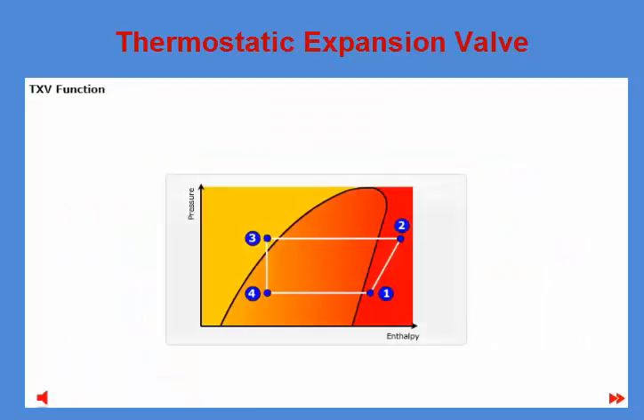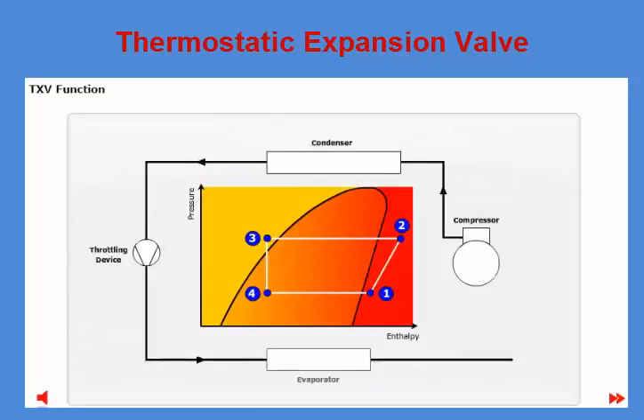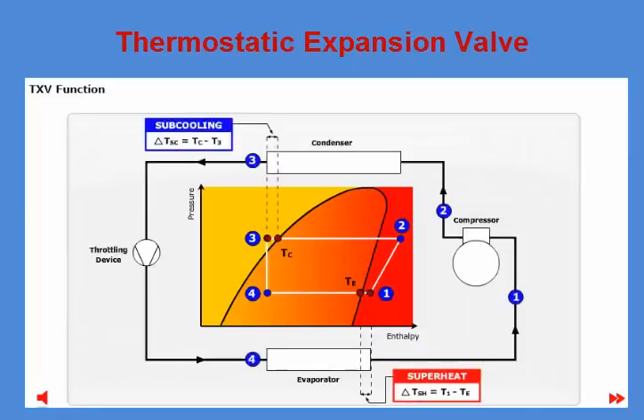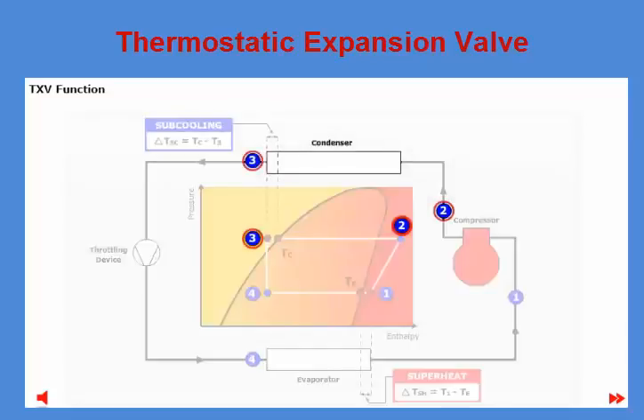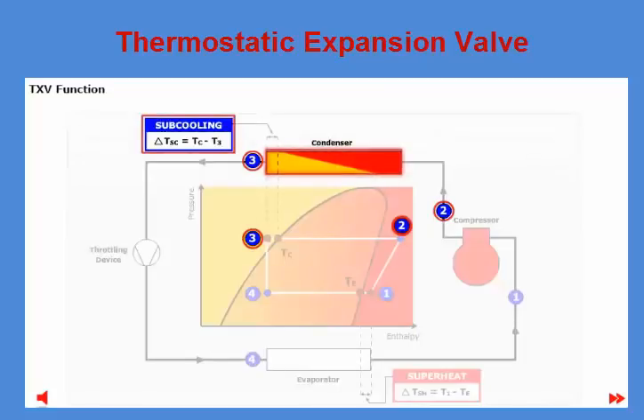This is a schematic of a refrigeration system showing what happens with the refrigerant in the four main system components. Between points one and two, the pressure of the refrigerant vapor is increased by the compressor; refrigerant leaves the compressor as hot vapor at high pressure. Between points two and three, the refrigerant is cooled down in the condenser, condensing from vapor to liquid. Refrigerant leaves the condenser as a sub-cooled liquid; pressure is not changed in the condenser.